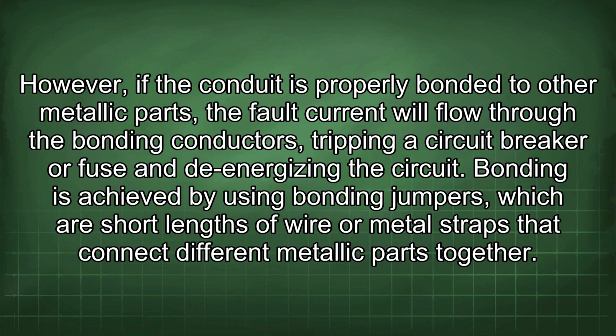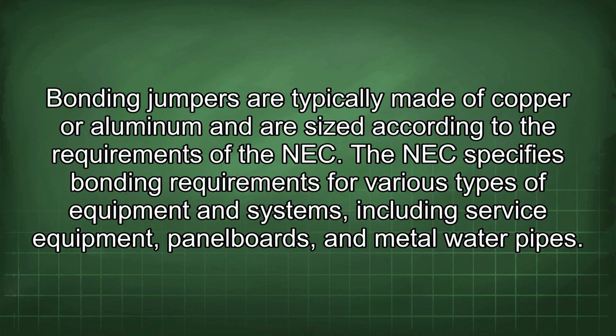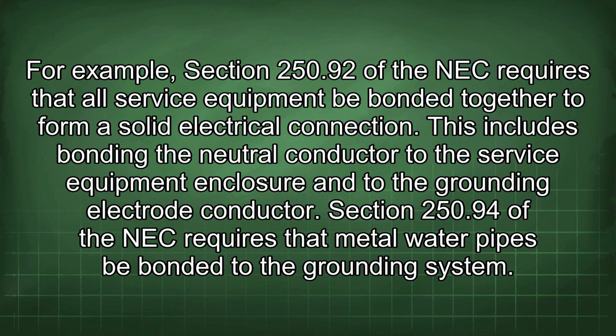Bonding is achieved by using bonding jumpers, which are short lengths of wire or metal straps that connect different metallic parts together. Bonding jumpers are typically made of copper or aluminum and are sized according to the requirements of the NEC. The NEC specifies bonding requirements for various types of equipment and systems, including service equipment, panelboards, and metal water pipes. For example, Section 250.92 of the NEC requires that all service equipment be bonded together to form a solid electrical connection. This includes bonding the neutral conductor to the service equipment enclosure and to the grounding electrode conductor.